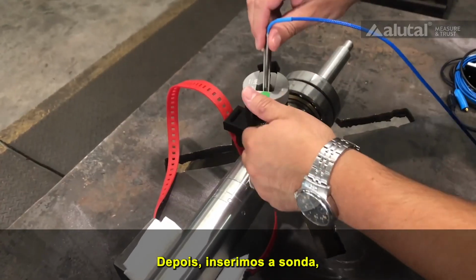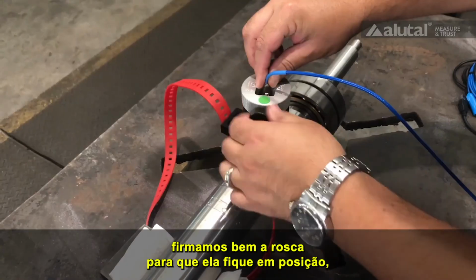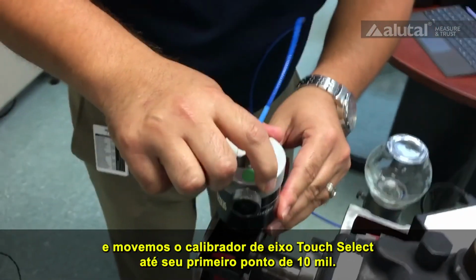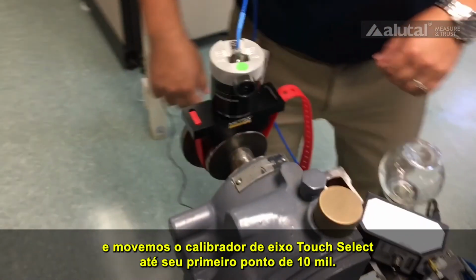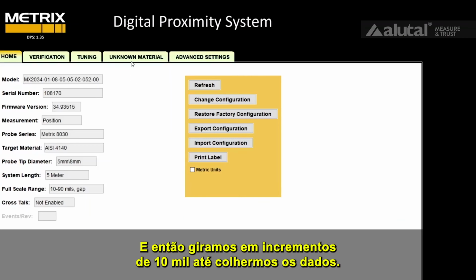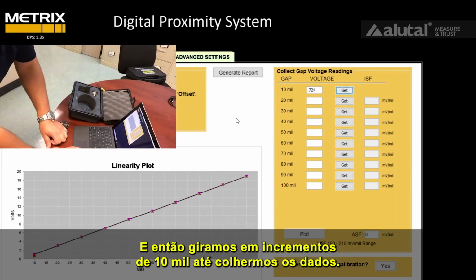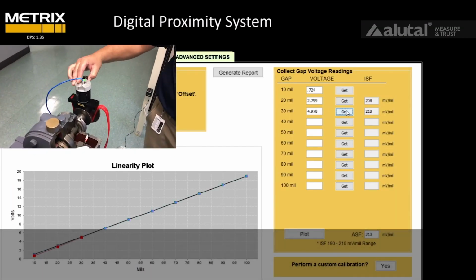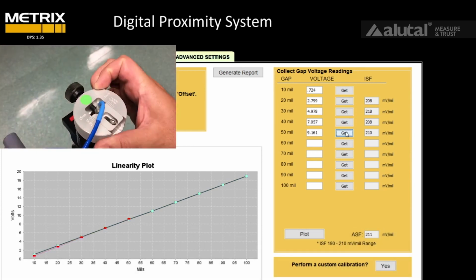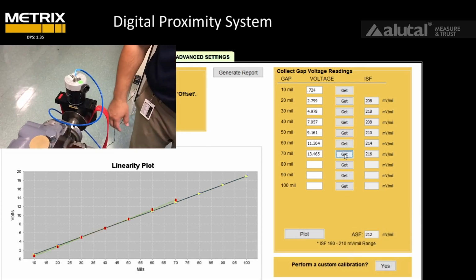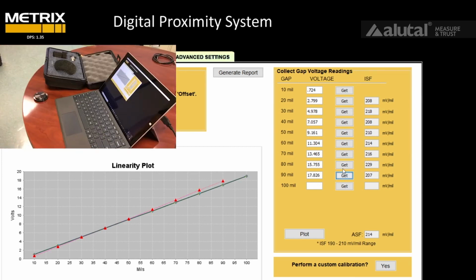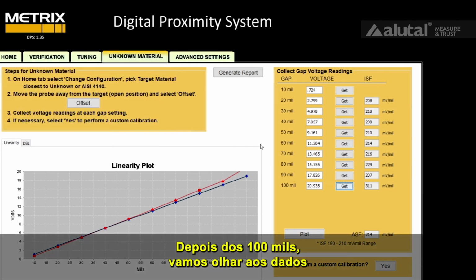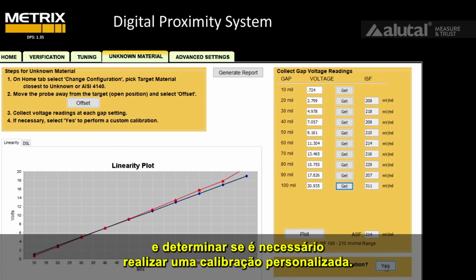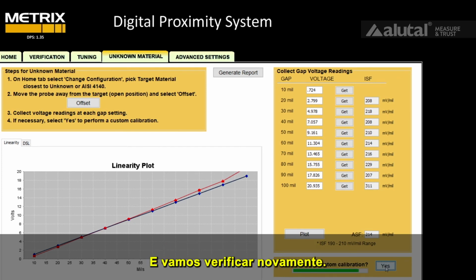Then we insert the probe, we tighten down the adjustment knob so that it stays in the right position, and then we move the shaft calibrator touch select to its first 10 mil point. Then we move it in 10 mil increments until we have the data. After 100 mils, we'll look at the data and determine, do we need to perform a custom calibration? And we will perform the verification over again.